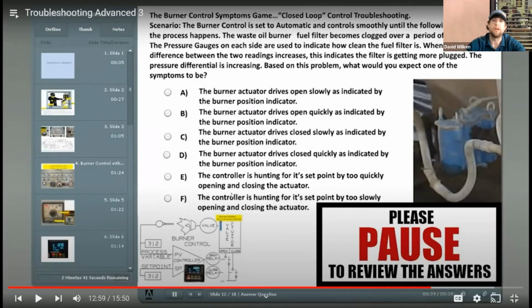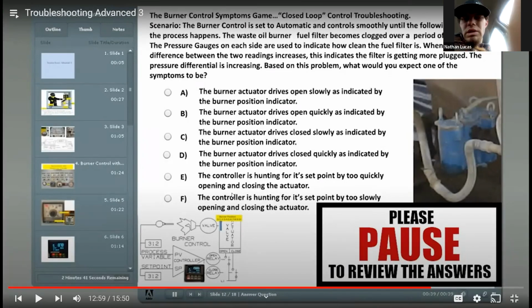Isaac, what do you think is going to happen here? Filter's clogging up over several hours. Okay, so the burner actuator drives open slowly as indicated by the burner position indicator. The burner actuator drives open quickly. So since it's not happening right away, it's obviously going to move slower, but the actuator is going to open up slowly.